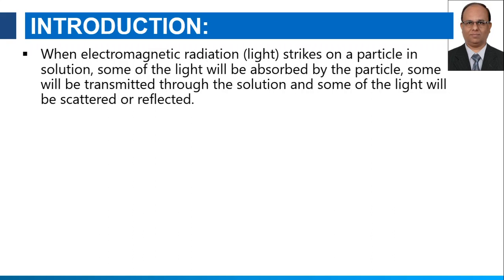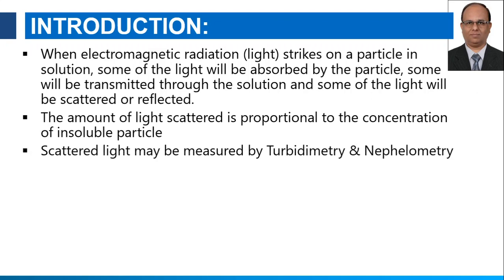In Nephelometry and Turbidometry, when electromagnetic radiation — or light, since we are in the visible region — strikes particles in a solution, some of the light will be absorbed by the particle, some will be transmitted through the solution, and some of the light will be scattered or reflected. The amount of light scattered is proportional to the concentration of insoluble particles, so we can use this technique for quantitative estimation. Scattered light may be measured by Turbidometry and Nephelometry.